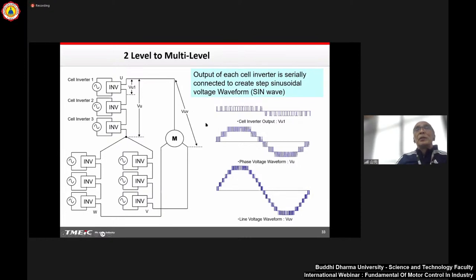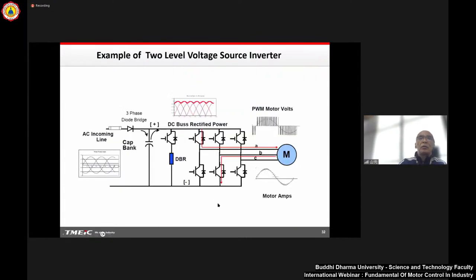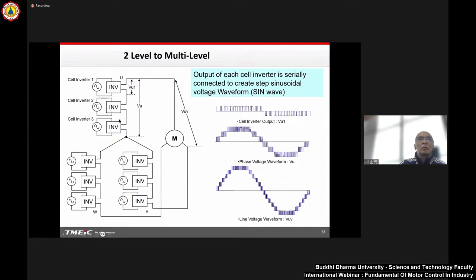So now, medium voltage drives consist of single inverter units connected in series like this. One output is just like this - very simple two-phase, single-phase output voltage. Combined with three voltages with a phase shifting, one phase output becomes three level: one, two, three level. Then phase to phase becomes three plus three plus zero, becoming one, two, three, four, five, six, seven levels. This is how we create medium voltage.